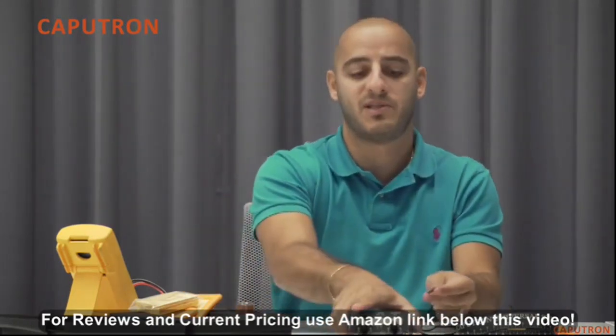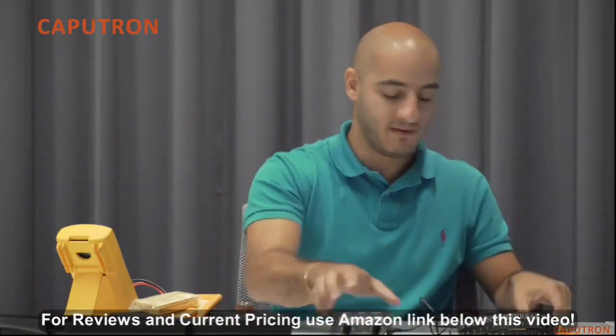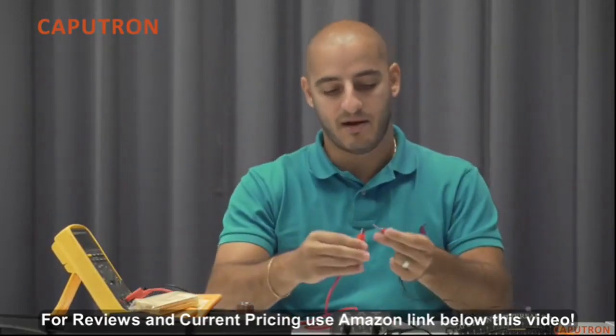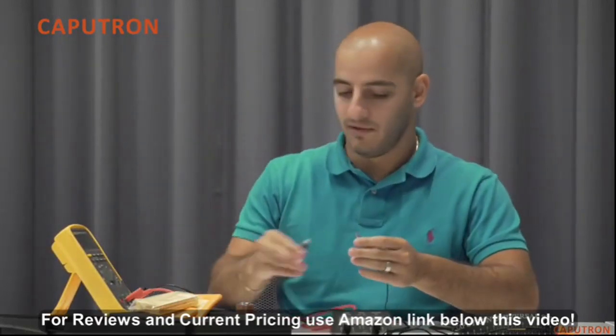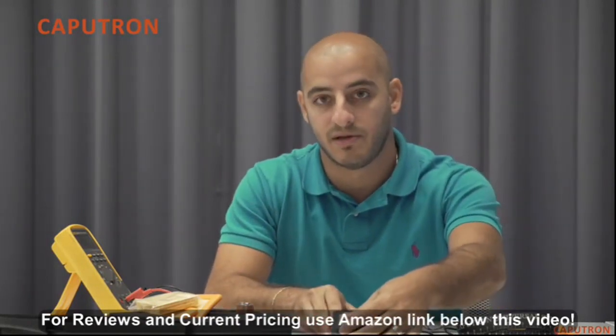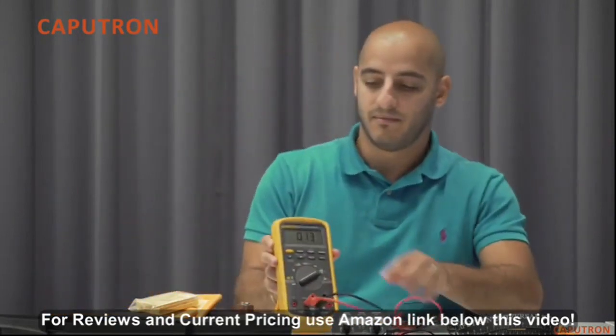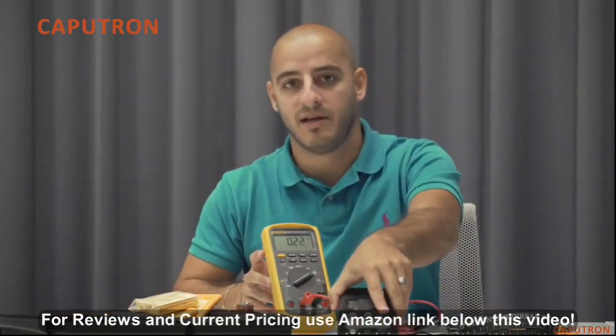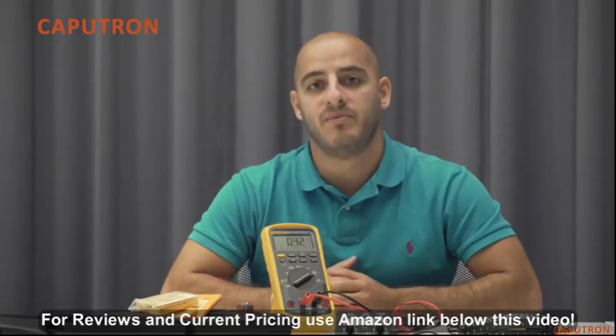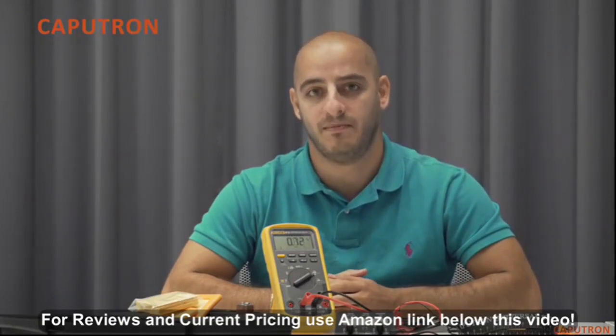Now, for the purpose of this demonstration, we will connect our device to a multimeter and simulate a closed circuit. Once we've connected the red anode and black cathode leads, we can set a current on our device and start stimulation. Now you'll notice on the multimeter, as well as on the device screen, the current begins to gradually increase. This initial ramp is extremely important in tDCS and helps your skin accommodate to the sensation of stimulation.